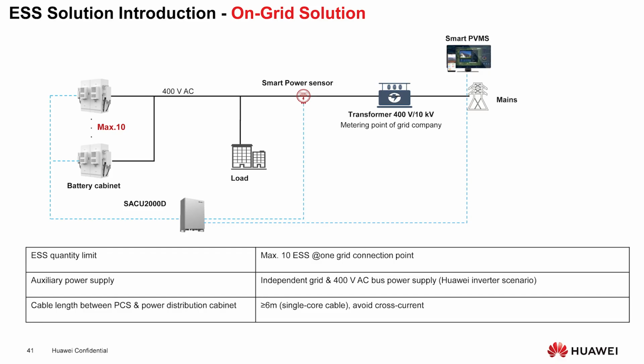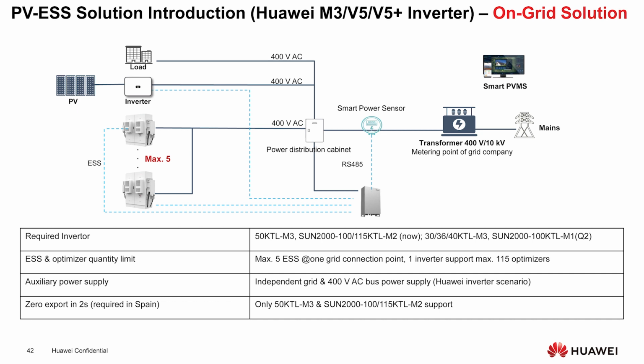Now we're introducing the solution with our M3, V5, and V5 plus inverters. These are all the new inverters that we're talking about. If you look at this scenario here, you've got your load, and your PV and inverter on the same line. You've got your ESS, which is a max of 5 units with PV on the same line, and you've got your power distribution cabinet here, which is also connected to your communication device, which is connected to your power sensor. And then you've got your step-up transformer for the municipality. This is also a very simple on-grid solution with PV. So these are only for where there's no load shedding.